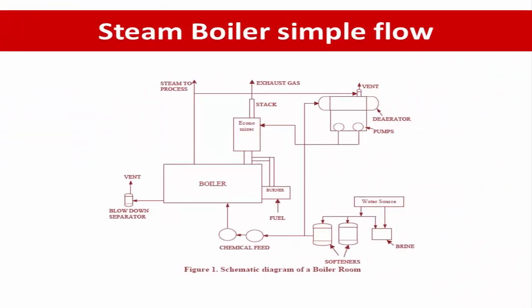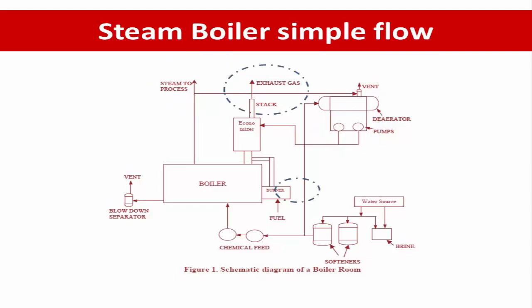The first input is water, where the terminal point will start at the non-return valve upstream of the economizer or drum. The first output is the product steam at the main steam stop valve or non-return valve. The second input is air, produced from the forced draft and primary or secondary air fans. The second output for air is the exhaust gas, as the induced air fan discharge.